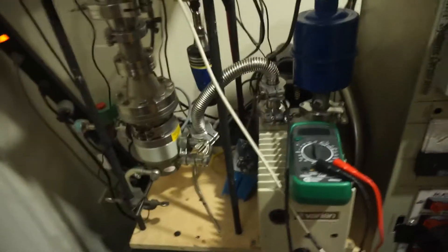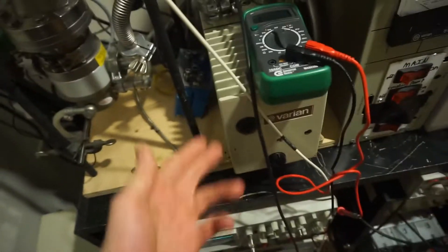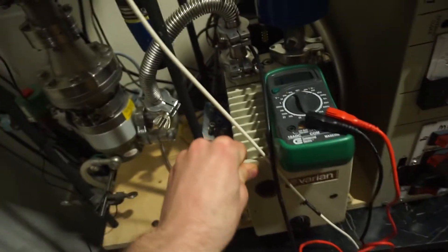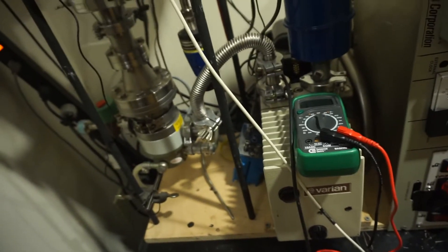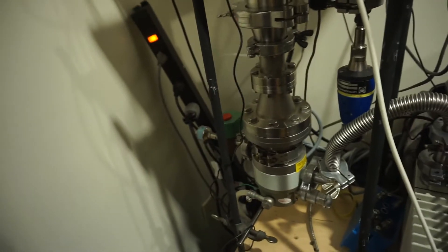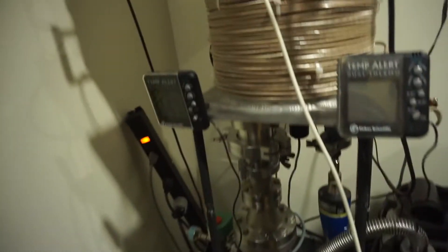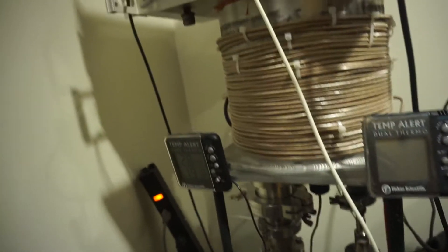So now we'll check out the vacuum system. So it's a two-stage high vacuum system. One and a half liter per second roughing pump. Pretty standard. Then we have a 56 liter turbo-molecular pump, which is probably getting 10 to the minus 6 torr under the setup pretty easily.